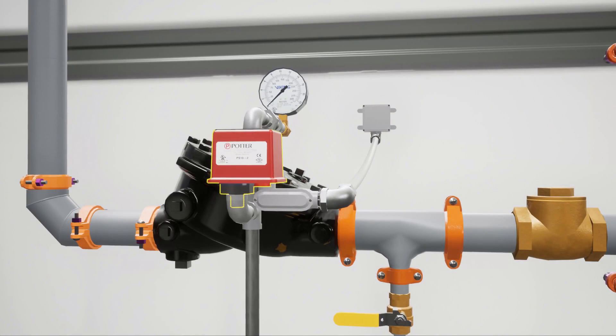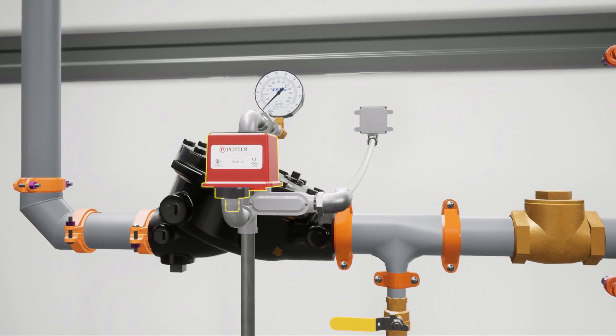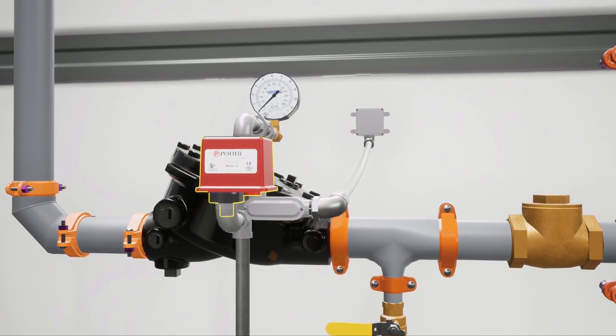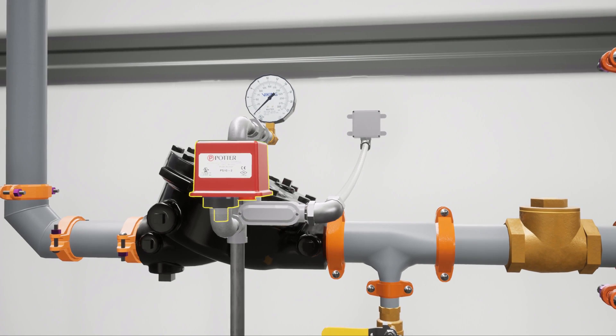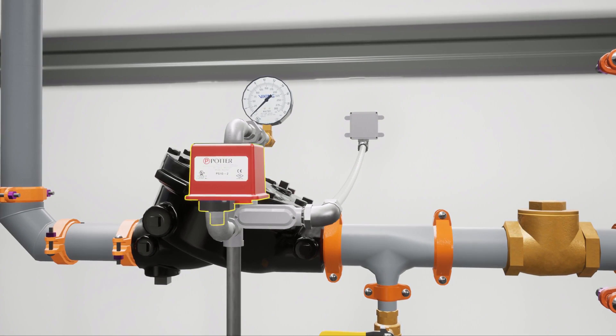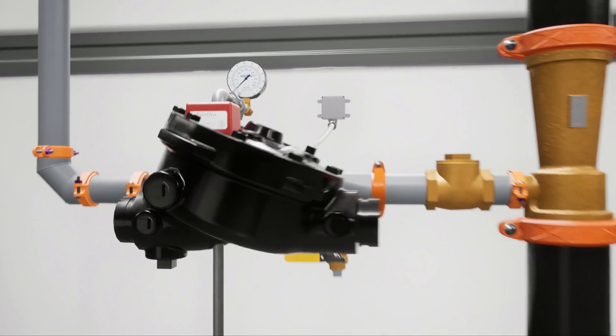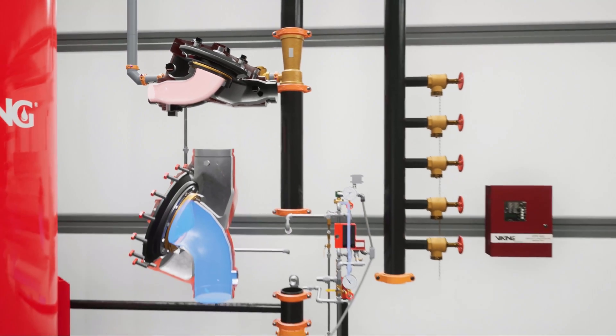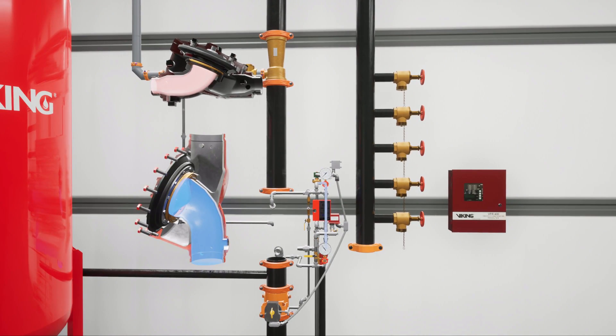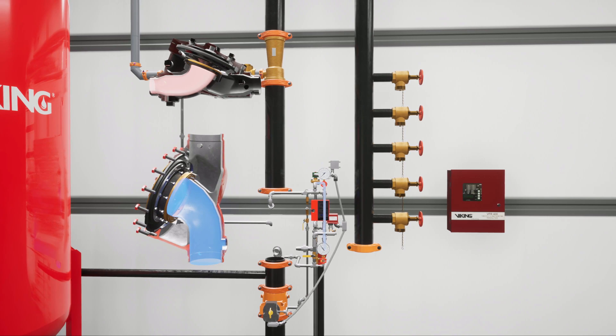The drop of prime pressure causes the priming pressure switch to activate. Priming line pressure switches are required for factory mutual global approval. After the release of prime pressure, the deluge valve's clapper and the concentrate control valve's clapper open simultaneously.